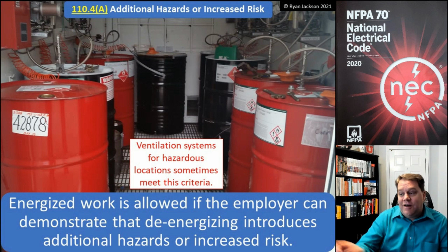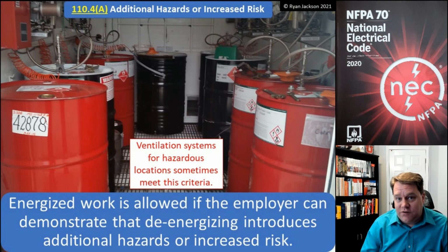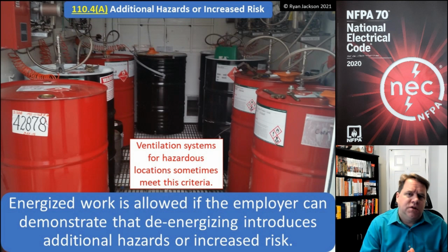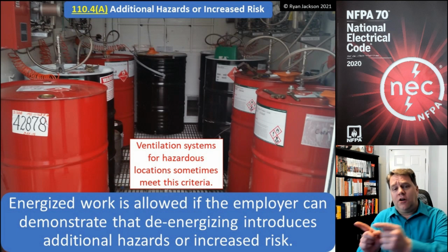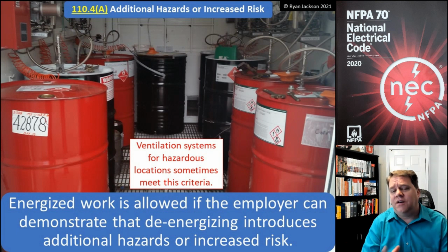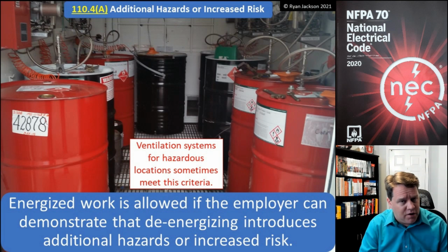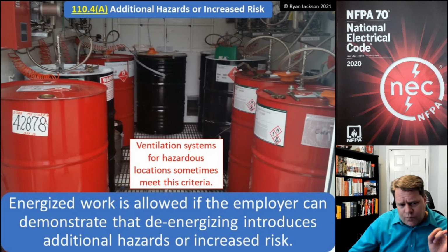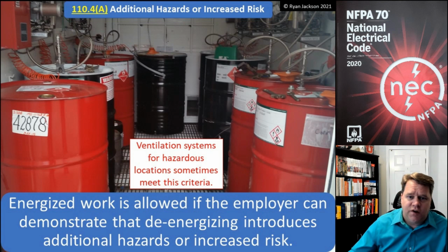So forget shutting off the breaker for 10 minutes while I do this task. We might end up blowing up a switchboard, and then you're out several weeks before we can get another one ordered. So usually, if you can explain to the owner of the facility the difference between a scheduled outage and a non-scheduled outage, usually you can explain that scheduled outages are very much preferred to an unscheduled outage. So I can work energized if we can demonstrate that shutting it off introduces additional hazards or increased risk. But again, I don't think that's something that comes up too terribly often, or at least it shouldn't.